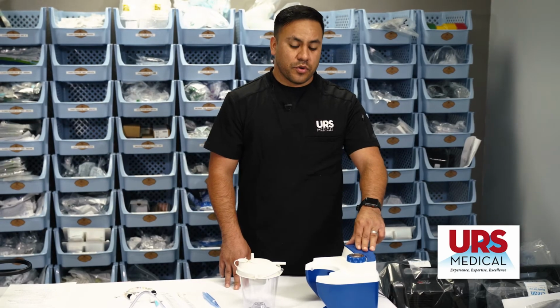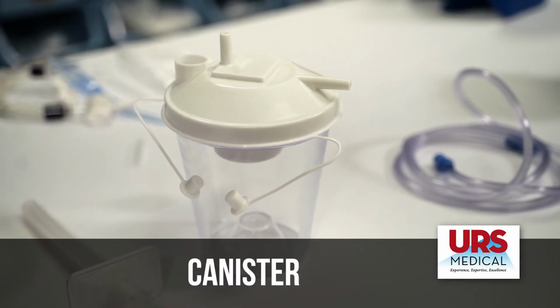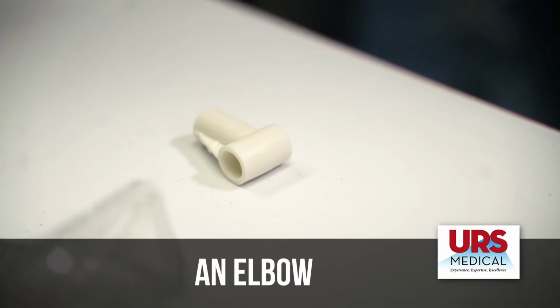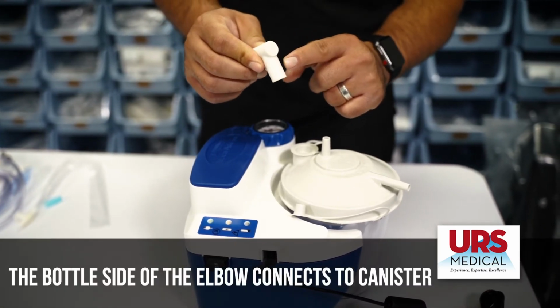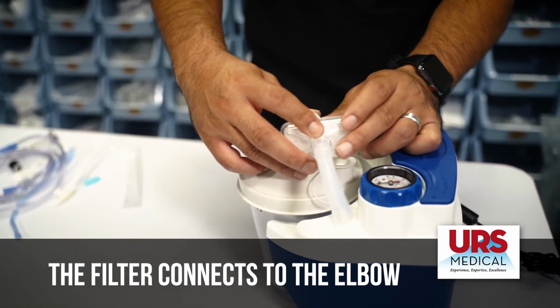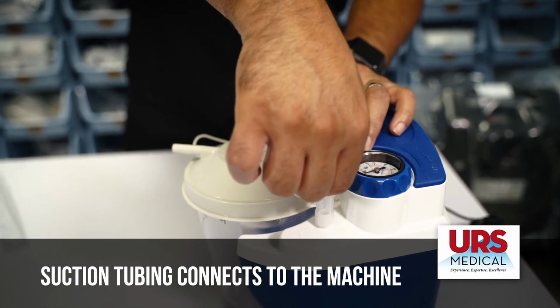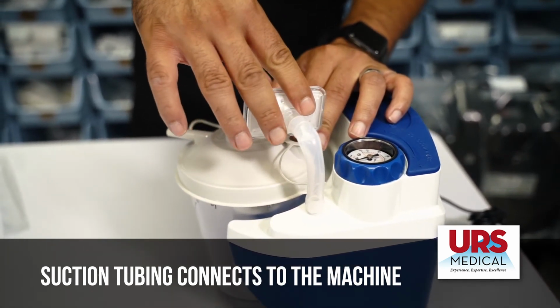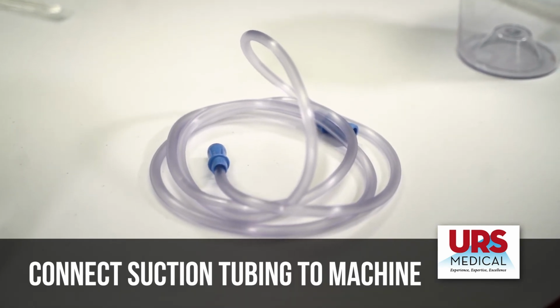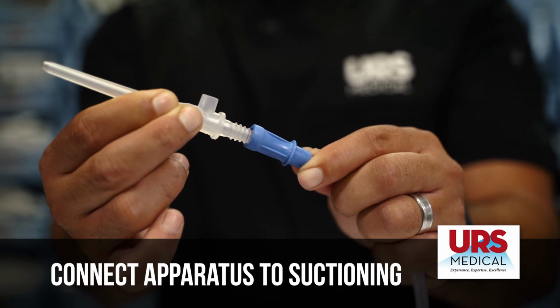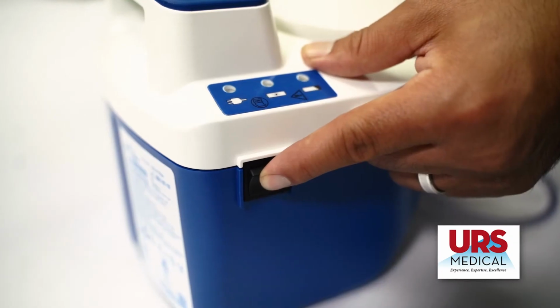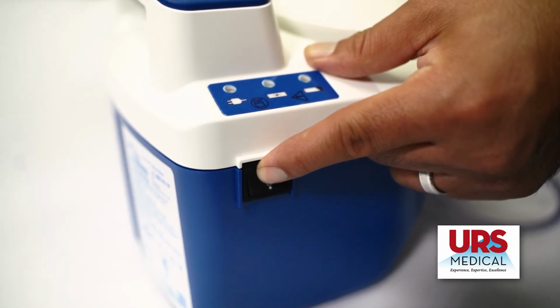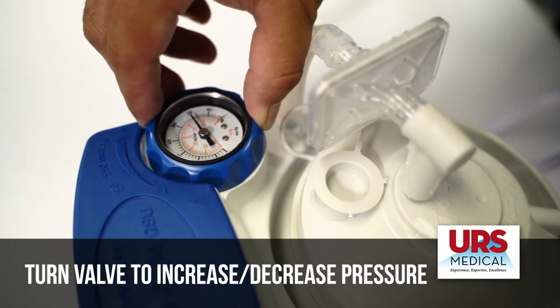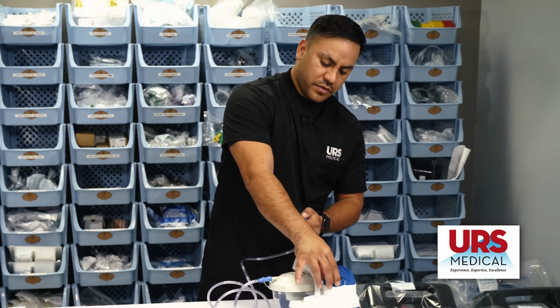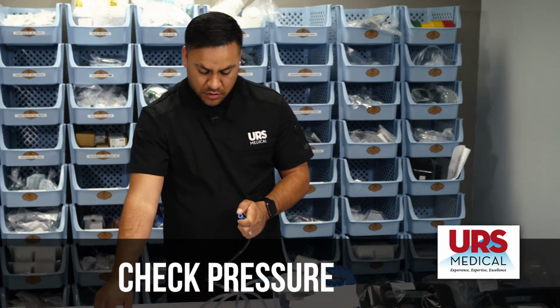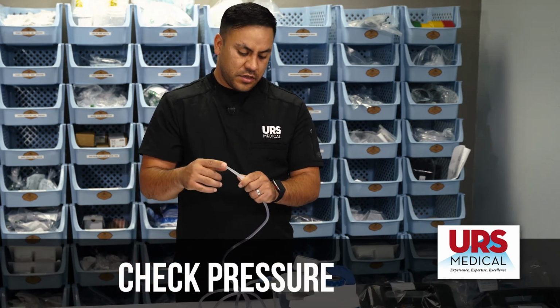Okay, so this is the portable one. The same way you would need a canister, an elbow. On the elbow it says bottle, so that would obviously go to the bottle. The filter connects to the elbow. The suction filter tubing connects to the actual machine. Next, you would connect your suction tubing and then the apparatus that you would use to suction. In this case, it will be a neo-sucker. You would then turn on the machine and then it would increase the pressure. You would go on the positive side and they would give you your reading. Here we're showing 100. You can connect your apparatus and you're still getting 100.